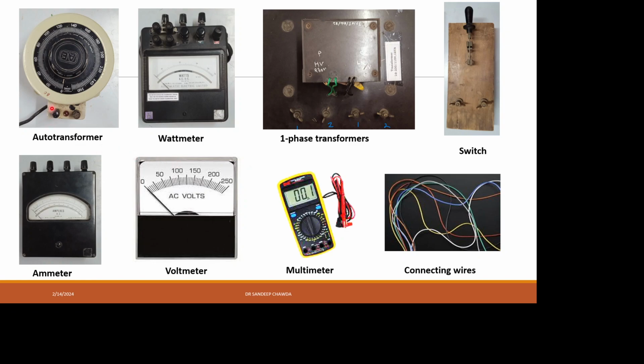This is the auto transformer, single phase auto transformer. This one is the wattmeter, single phase transformers, a switch, ammeter, voltmeter, multimeter, and connecting wires. Please note that all the measuring instruments should be AC, because the transformer works on AC.